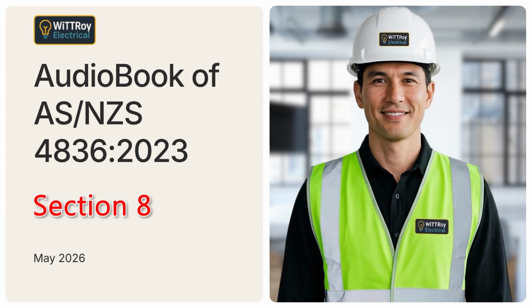The clause also reminds us that ladders that are damp or dirty can become conductive. So, a ladder that is normally non-conductive may still become dangerous if it is wet, muddy, contaminated, or damaged. In simple terms, check the ladder before use. Check the material, check the condition, check for moisture, dirt, damage, and contamination. Do not use a ladder around electrical work if it may become part of the electrical path.